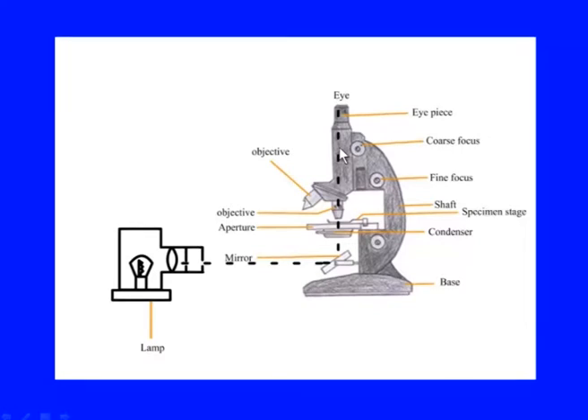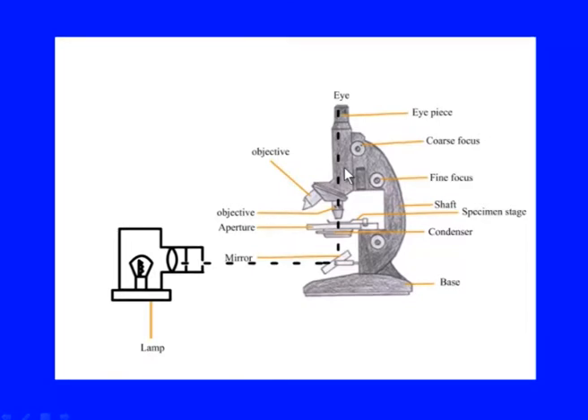The mechanical tube length is fixed, and there are two kinds of optical systems: finite optical system with a fixed tube length, and infinity corrected optical systems. It is very difficult to insert auxiliary components in a finite optical system due to aberration and image formation problems. In an infinity corrected system, auxiliary components like prisms or polarizers can be inserted without any image problems.